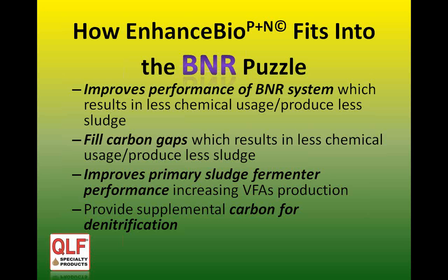How EnhanceBio fits into the EBNR puzzle. There's 4 different things we can do to improve the performance of the EBNR system. We can fill carbon gaps. We can improve primary sludge fermentation performance, and we can also provide carbon for denitrification. In the upper 2, what happens is when you use our product, you use less chemical and you produce less sludge.